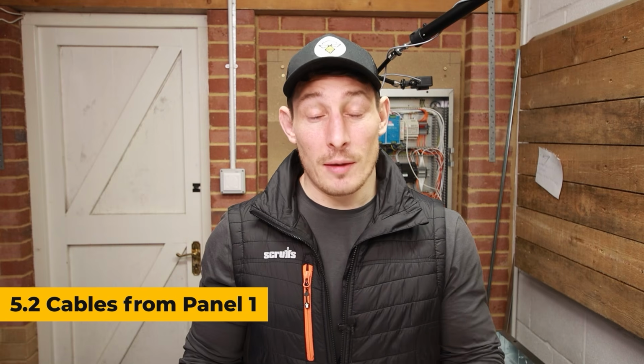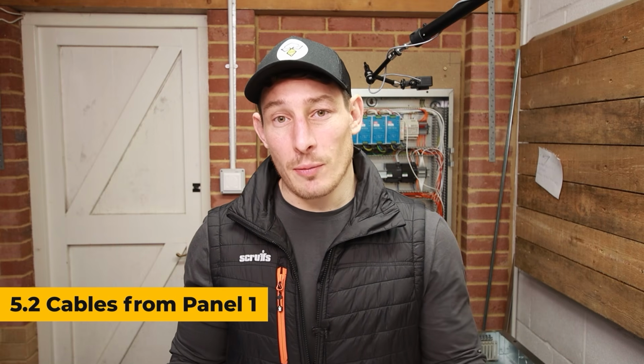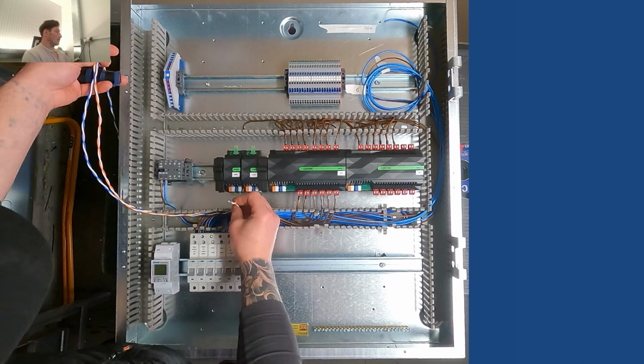Okay guys, on to the next stage of the wiring now, focusing on the inbound cables from LOX 1 into LOX 2. Those cables are the 24 volt DC supply going to the additional extensions within LOX 2, and also the continued Loxone link bus, remembering to put a 120 ohm resistor at the end of the last extension.